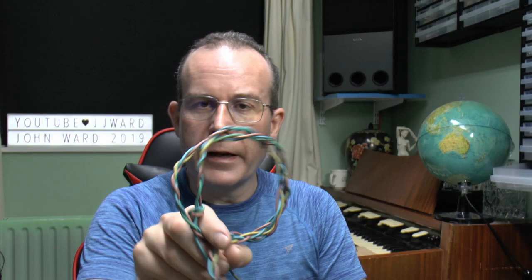So faulty flex there, and faulty over quite a short length here. And the particular installation had a whole set of these lights, all of which had about a meter of this flex on. And oddly, some of them were like this, showing very poor readings. And the others were perfectly fine and no problem there whatsoever. So presumably two different batches of the flex, or put in at different times or something like that. And as I say, visually wouldn't have thought there'd be any problem with this, but clearly testing it showed up that it was really a load of old rubbish. And that particular installation, the end result was that the faulty lights had new flex attached, and the rest of the cabling was actually replaced as well with the junction boxes and things, because the original ones had basically filled up with water and were not in a repairable state. So it was just easier to replace what was there. So that was the end of that installation, and all fixed up and working. And it's also the end of this video. So until next time, thanks for watching.